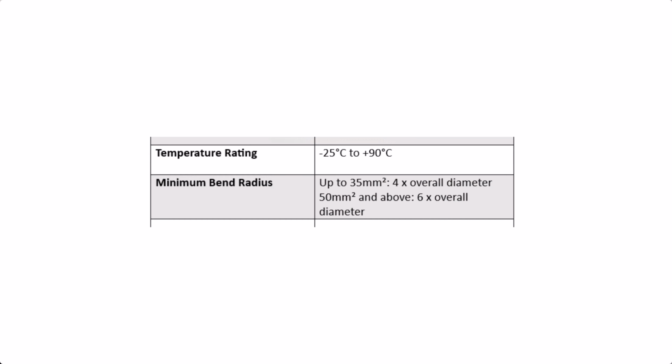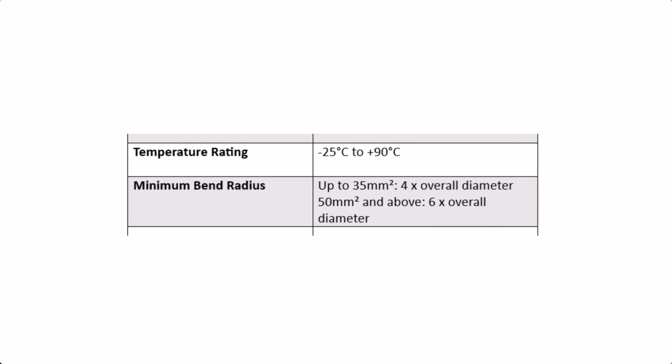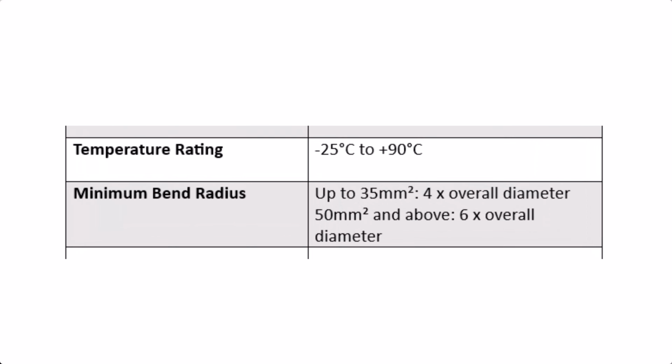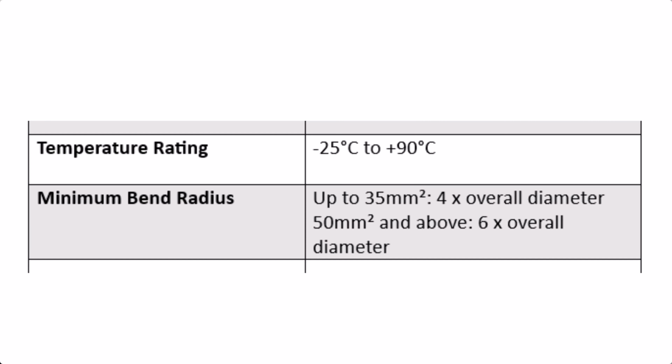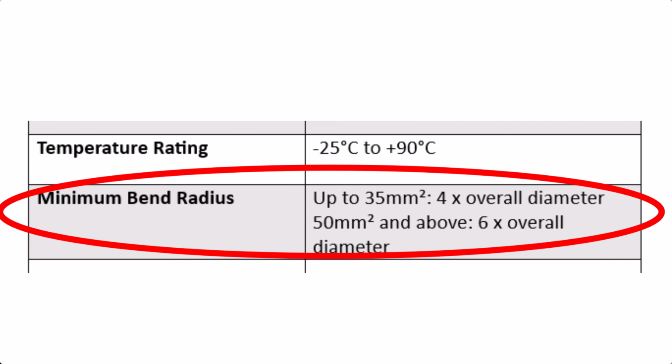Each cable has its own minimal bending radius. Using a smaller one could harm your entire electrical installation. The minimal bending radius is usually given in the technical specifications of any cable, particularly in the data sheet of the cable giving the physical characteristics.